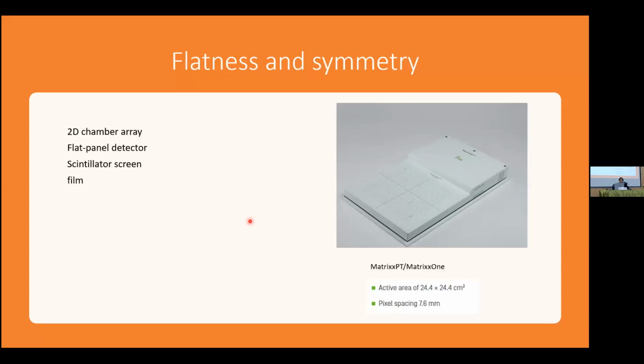Other things that you want to test. So this is a 2D chamber array, so flatness and symmetry. This is something that in photon therapy you're really used to checking. It might not make as much sense to check flatness and symmetry here, but this is a good way, if you have a standard field that you can put in there, to ensure that the scanning and everything else is still working properly, that you are able to actually scan the way you were scanning before, particularly if you're doing continuous scanning.